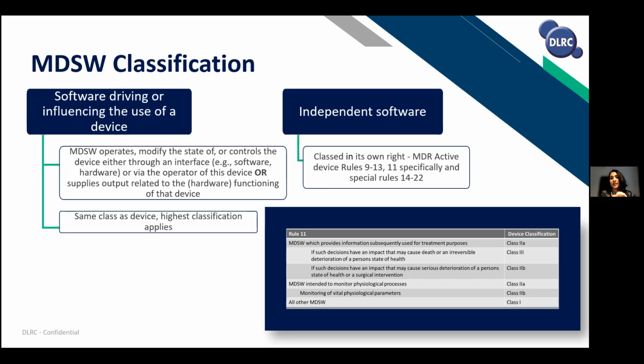However, rule 11 is quite specific to medical device software, and you would also have to consider special rules 14 to 22. In this case, I have already ruled out rules 9, 10, 13, and 14 to 22. So we only need to consider rule 11. Rule 11 basically covers any medical device software which provides information that is subsequently used for treatment purposes. And this places those types of devices into class 2A. So it's not the lowest risk, but it's not the highest risk.